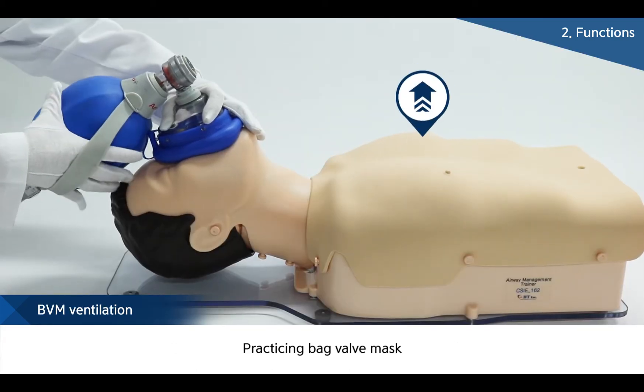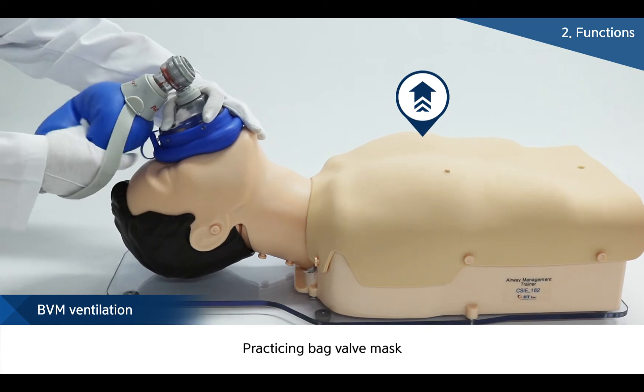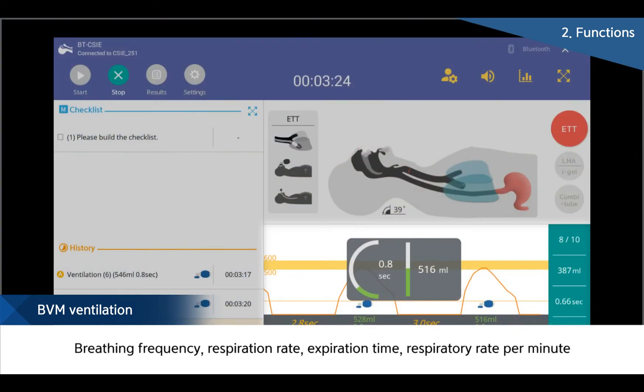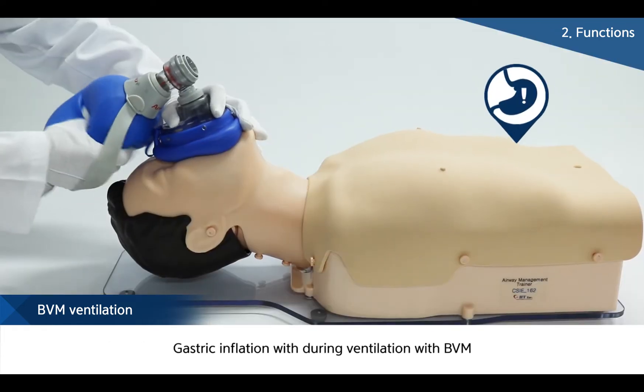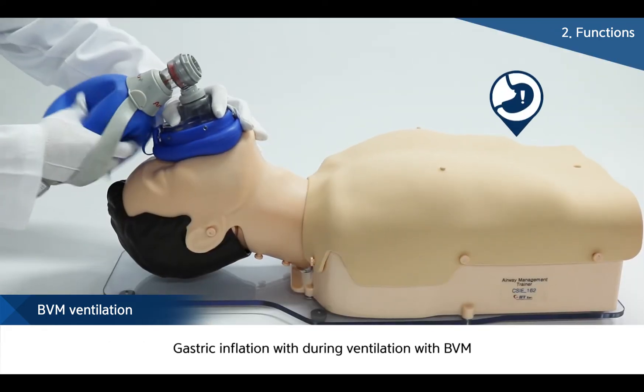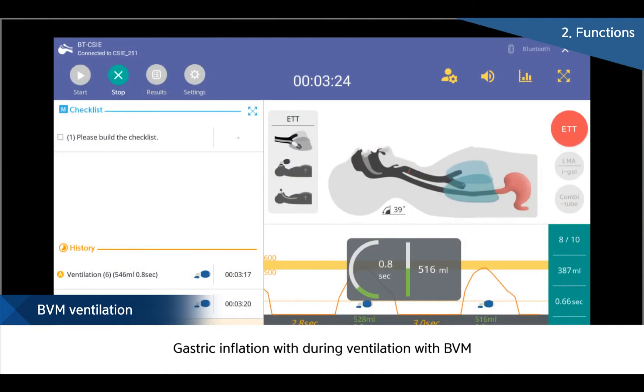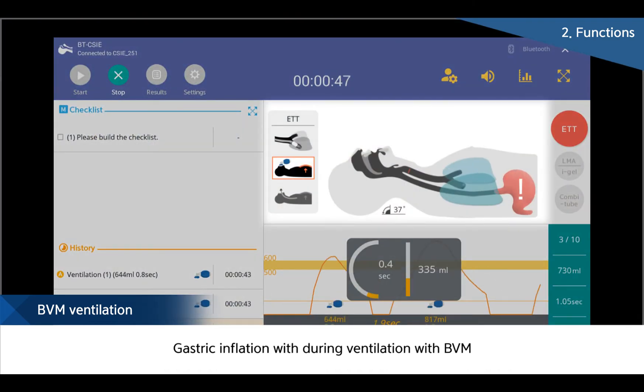During ventilating air by using a bag valve mask, volume, rate and time of air can be confirmed in real time on a screen. When ventilation has not been done correctly, gastric inflation can be displayed with the simulator and also on the tablet PC.